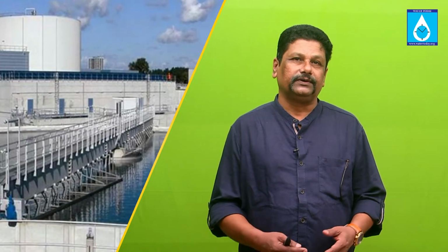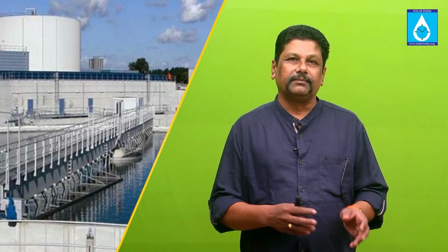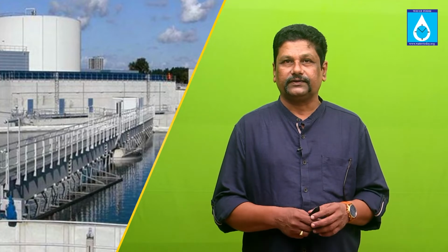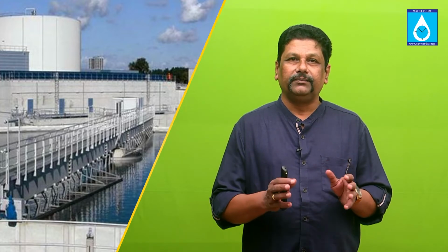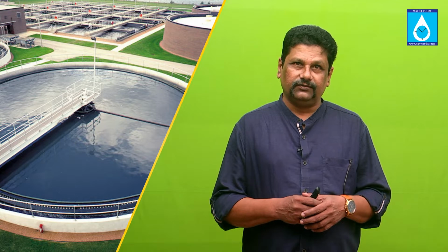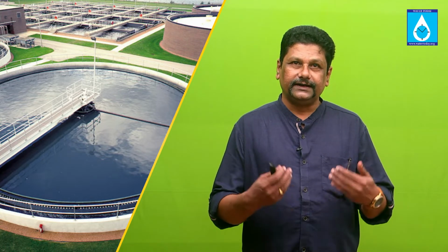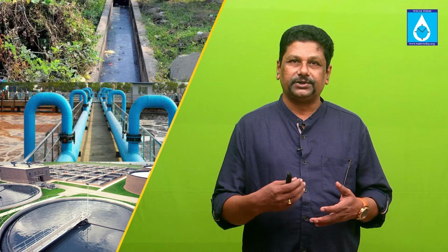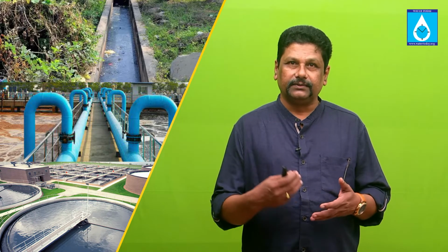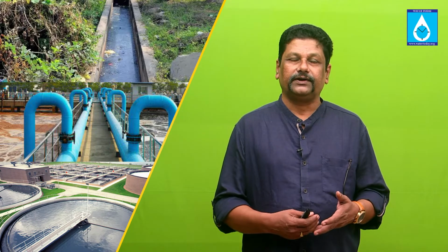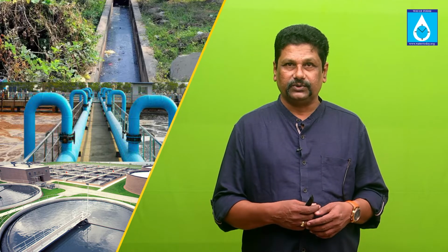Drainage is nothing but, for example, your car park in the basement, where you will have about 10 to 15 particle size. If you go to the next, which is effluent, which is predominantly in the industry, you will get about 35 to 45 of solid size. The toughest one, the sewage, you need minimum 80 of passage for pumps. So first identify whether you're going to handle drainage, effluent or sewage. Then remember this: 15 to 20 particle size, 35 to 40, and 80 and above for sewage.